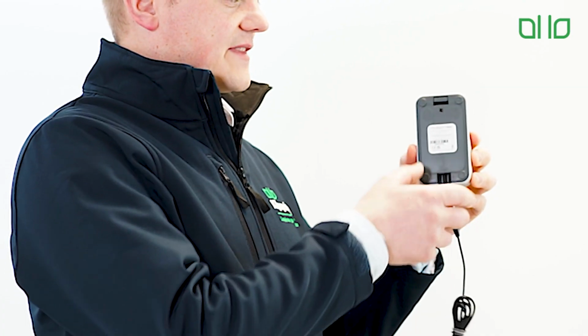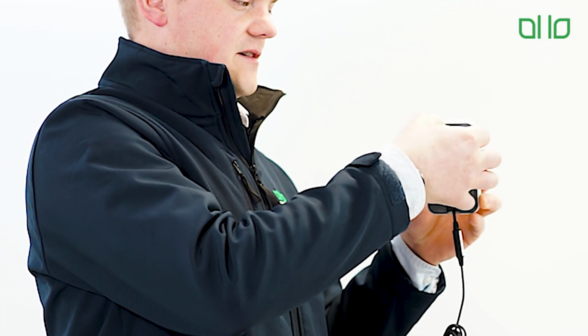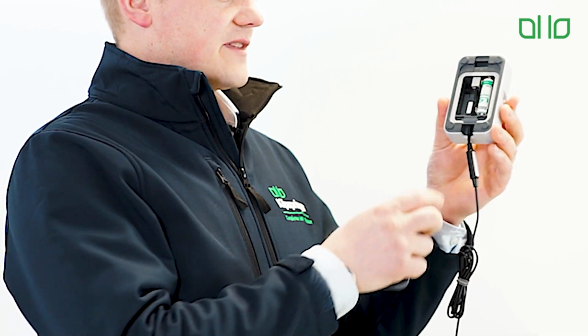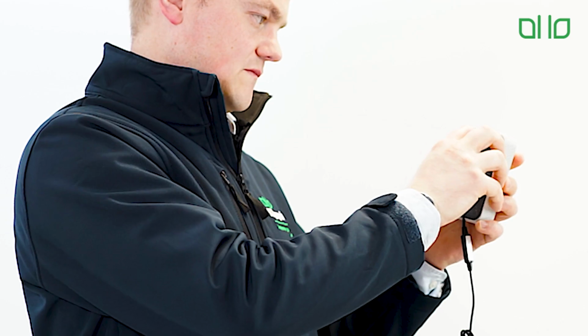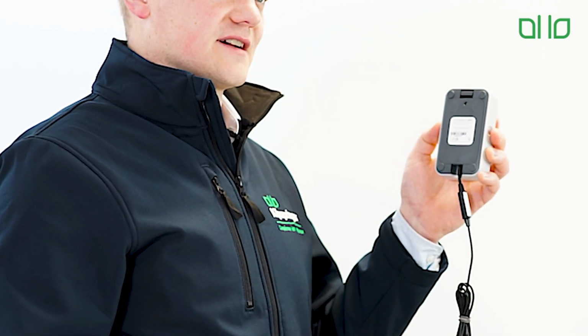To replace the battery, on the back of the unit is a replaceable cover. Simply unclip the cover. You will find the battery located. The battery specification is a 3.6 volt lithium AA size. Simply remove the battery and replace it with a new one. Reattach the cover, ensuring the waterproof seal is maintained, and listen for the clip when it closes. Press the button on the side of the transmitter again, and you should be looking for at least one green flash.